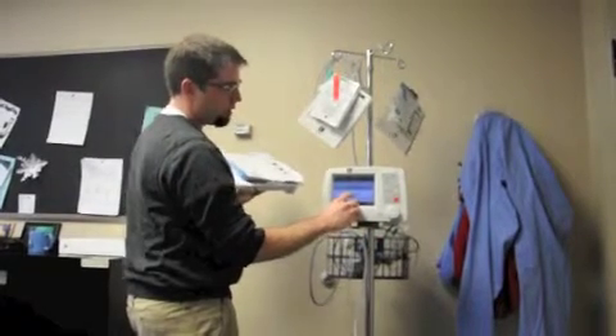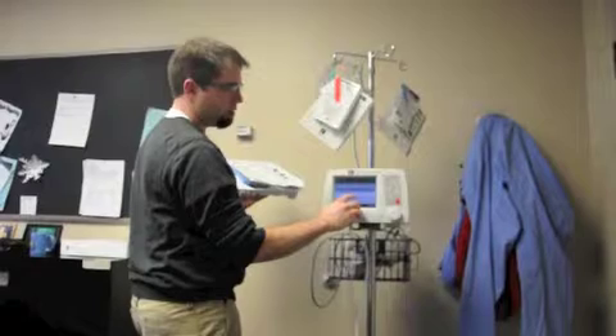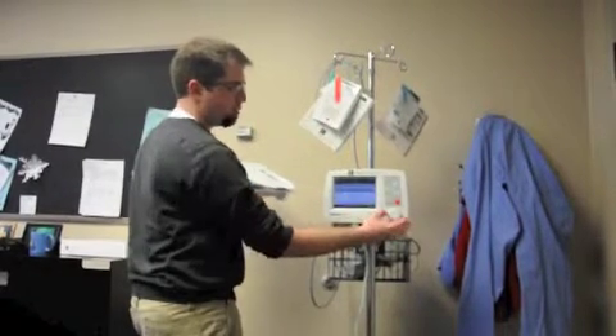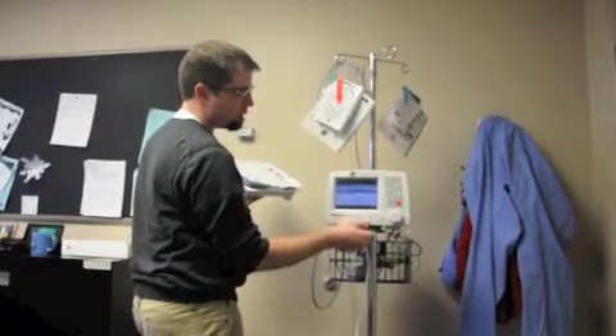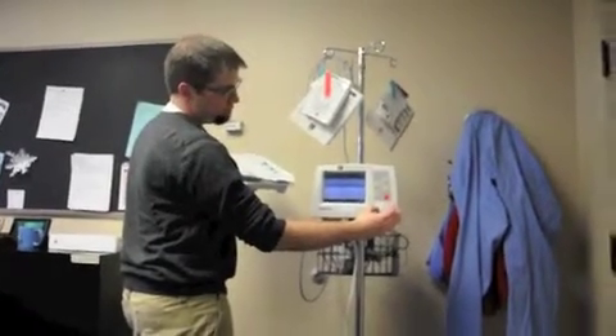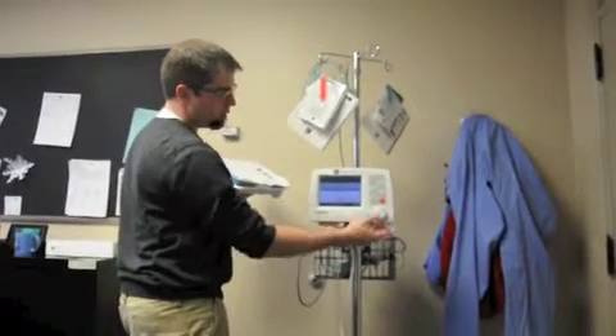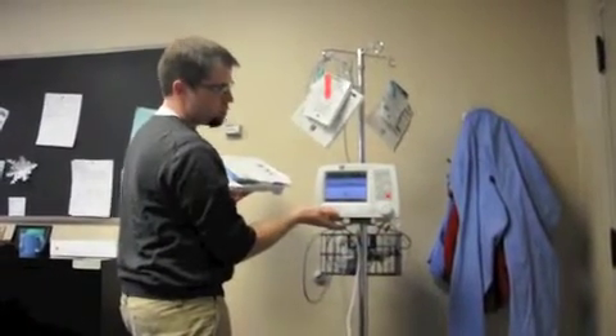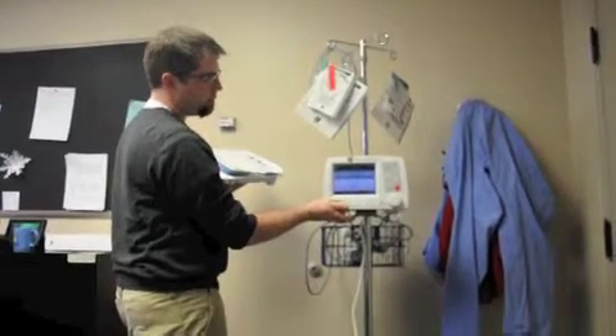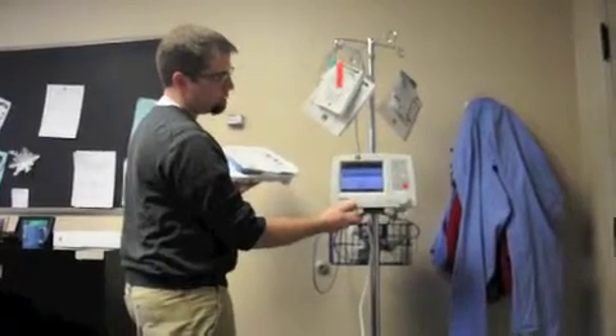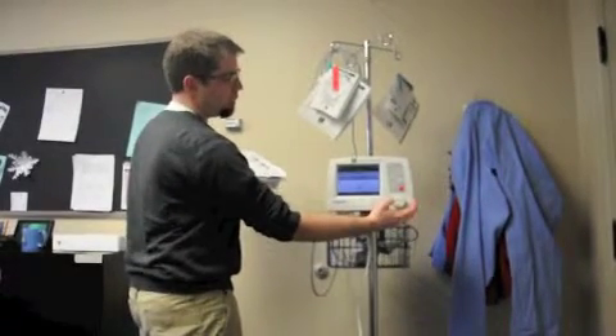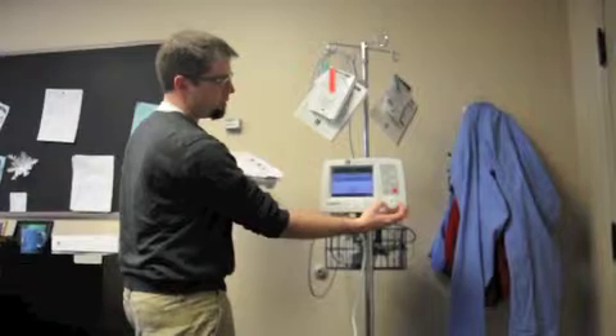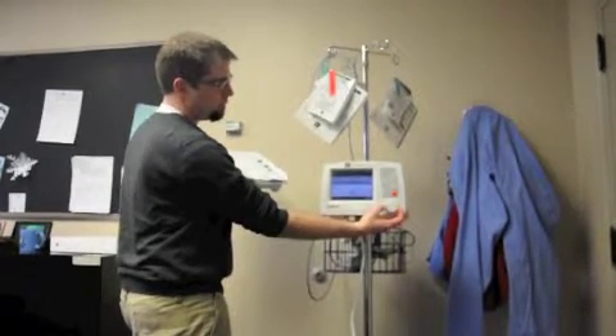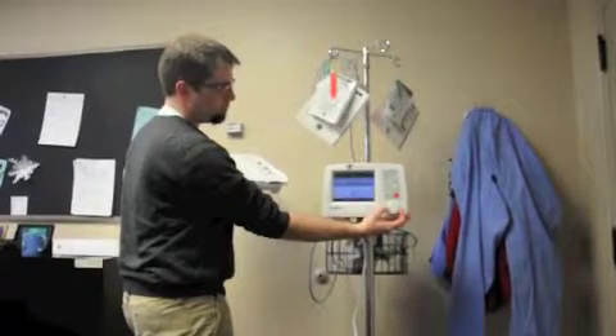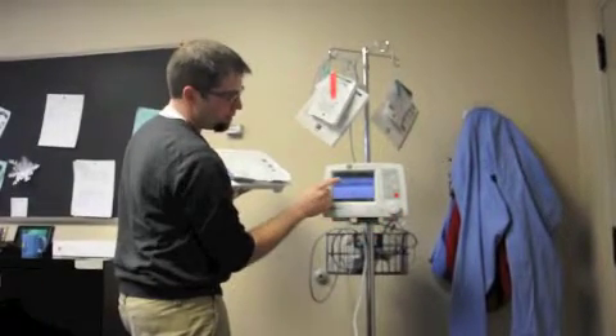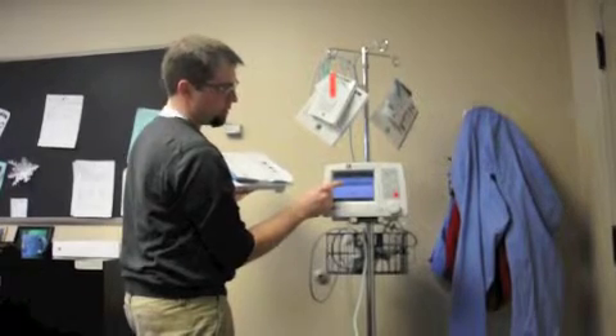At this time we can enter the hemoglobin. If we do have lab values from the patient that are recently acquired, we can use those, or they also have the factory defaults. Once we enter those numbers or use the defaults, hit calibrate. It takes about 20 seconds for that to calibrate. After that time, the physician can be prepping the patient during this whole time, so there really is not any delay in line insertion. Once that time is up, it says in vitro calibration OK. Insert catheter, then select start.